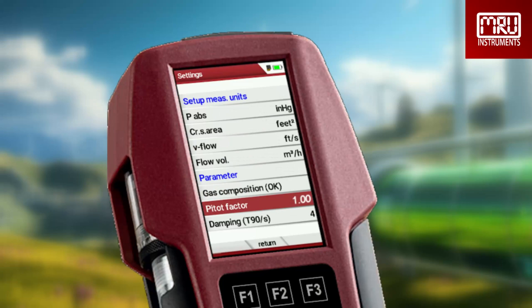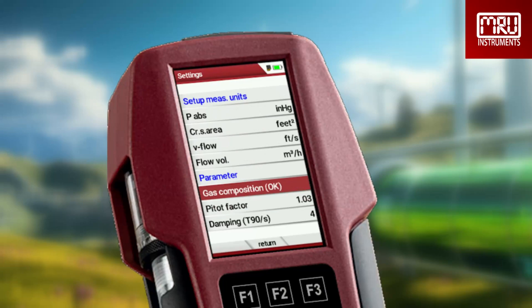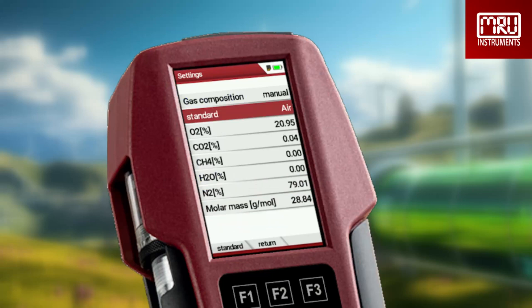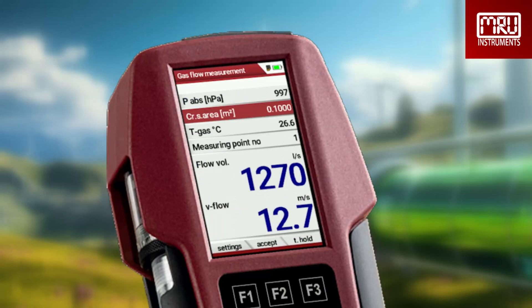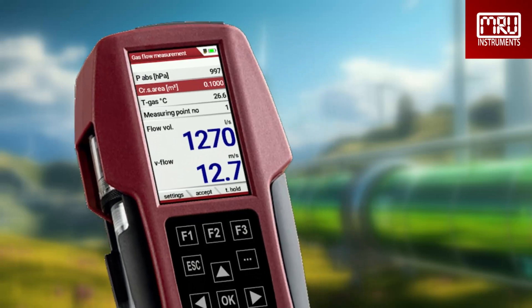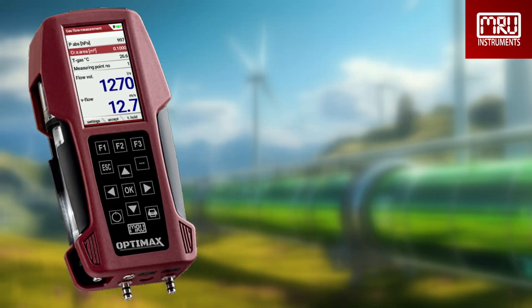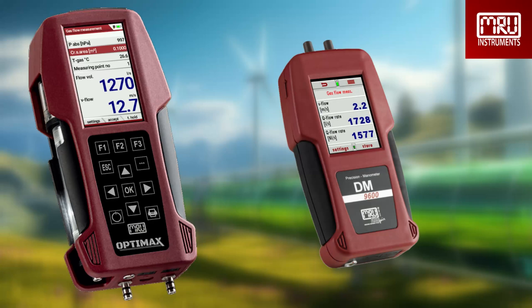For correct calculations, the pitot factor must be set as well, where the L-type tubes have a factor of 1 and the S-type tubes have a factor of 0.84. Even the gas composition can be manually entered if known. The flow velocity option can be retrofitted in most of our analyzers. This can be done at our Texas location. Please feel free to contact us if you would like to learn more about flow velocity measurement and the possibility to upgrade your analyzer.